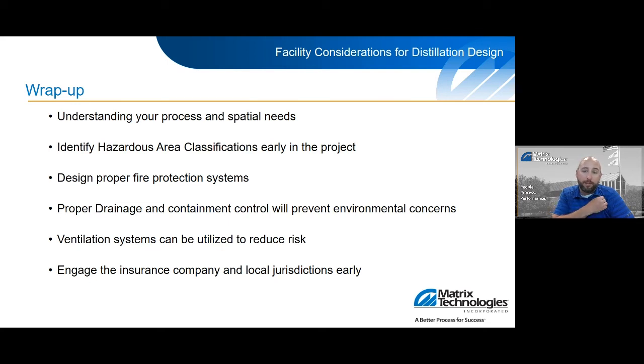And then ensure the means and methods for your containment. Identify those source points of where your leaks could be, look at your largest tank volume, and then also go back to your fire protection. That's going to be really the driver for your containment area. And ventilation, make sure you have the proper ventilation. Exhaust is critical, and then detection in your facility. The last thing you want is to pool up all these vapors in your building, and somebody flips a light switch and things don't end well there. So make sure you keep that into consideration, and your backup systems for that too, in the event of a power failure.